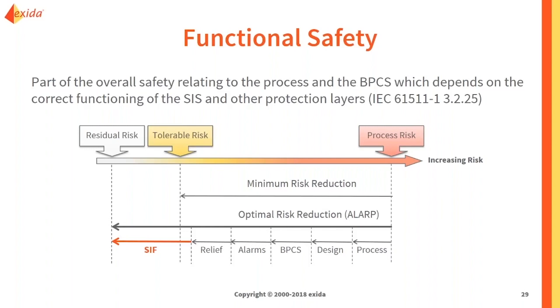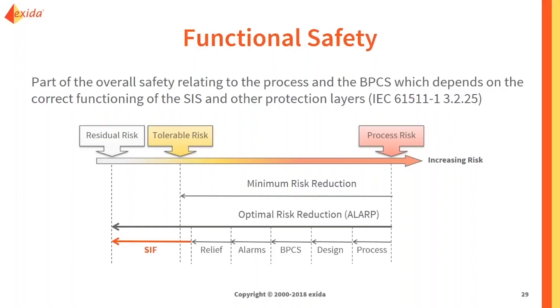There are many ways to achieve risk reduction. We can make changes to the process — if there are lower quantities of explosive materials, explosions will be smaller and effect zones will be smaller. We could change our overall process design; if leaking pipes is an issue, maybe we use dual wall piping. We may have a control system implementing an interlock, an operator responding to an alarm, or a relief device that releases pressure from a vessel.